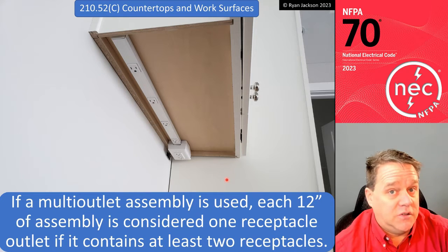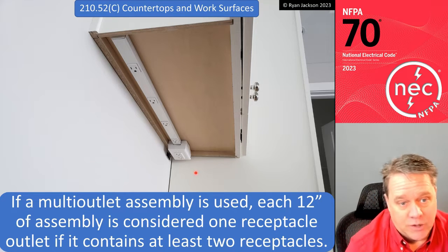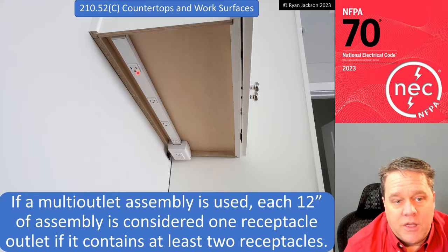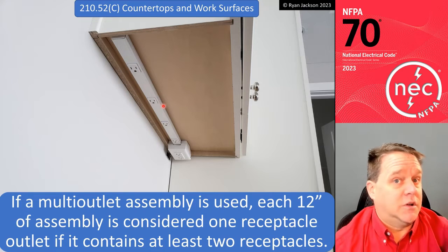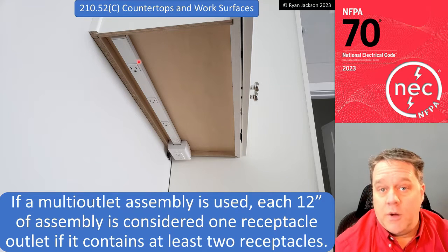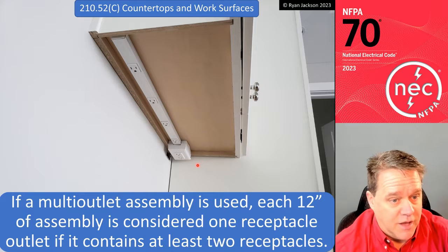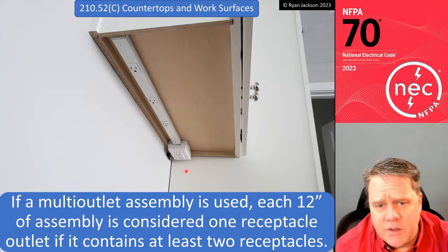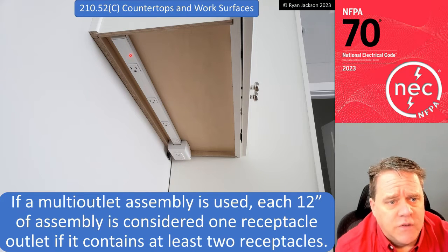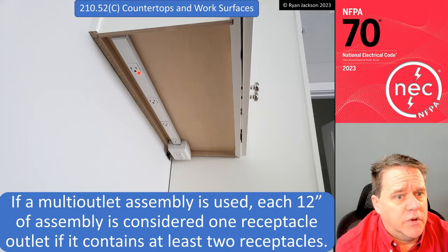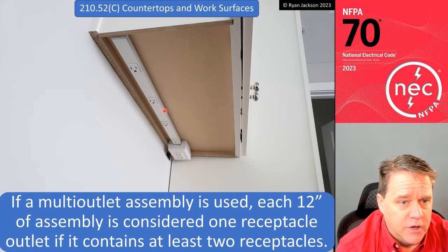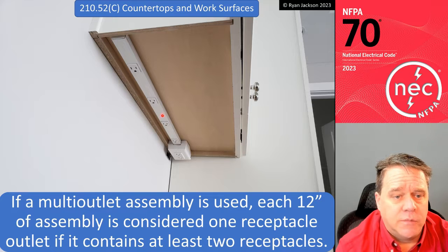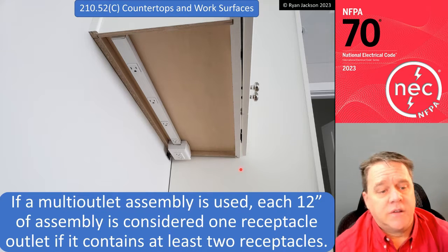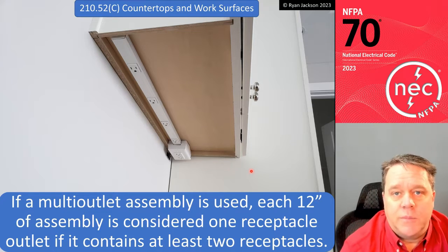So they made a change in 2020 to clarify. Look, if you have multi-outlet assembly like this, yes, that's only one receptacle outlet, but it's a whole bunch of receptacles, and that's compliant. So if a multi-outlet assembly is used, each 12 inches of assembly is considered one receptacle outlet. So from here to here, one receptacle outlet. From here to here, another receptacle outlet, as long as it contains at least 2 receptacles. So we're good.